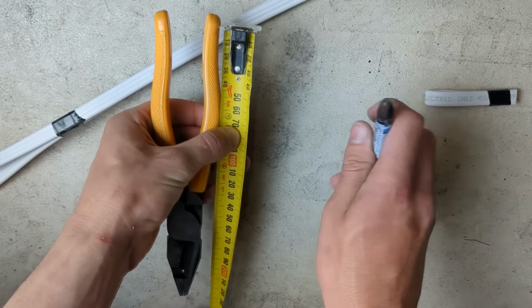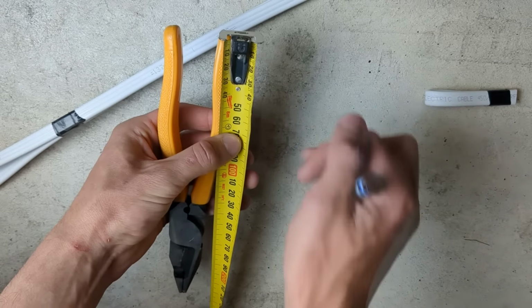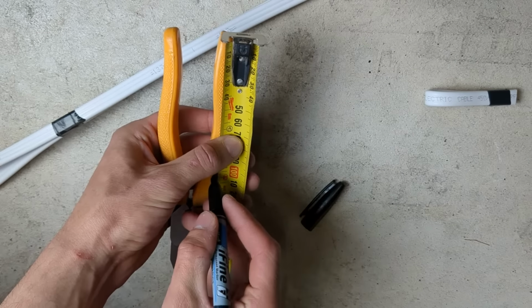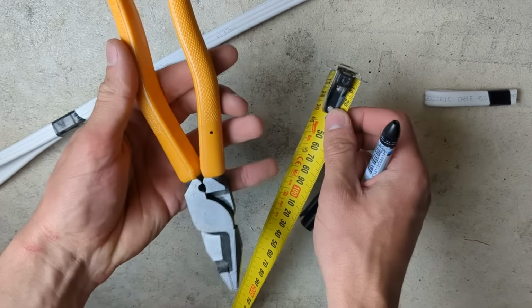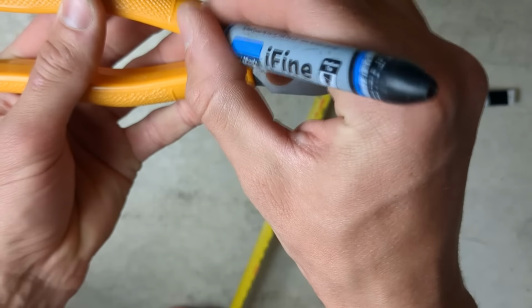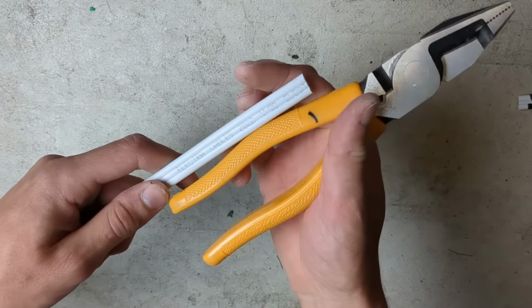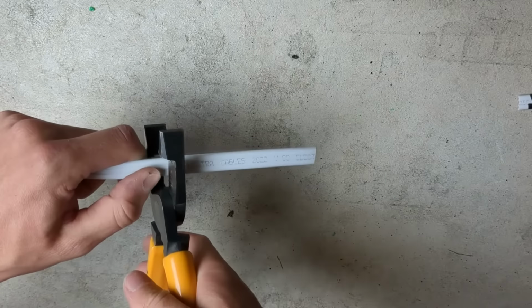Clause 3.10.1.1 and then note 2, I think it is, gives you the minimum requirements of unsheathed cable behind a hole in a wall. For example, you cut out your hole for your power point. A good way to make sure you're not going above 100 mil is to get your pliers out, measure 100 mil on them and mark it with your texta. Every time you strip cable for a power point, you put that mark next to the cable and you know your cabling is complying with the AS3000.